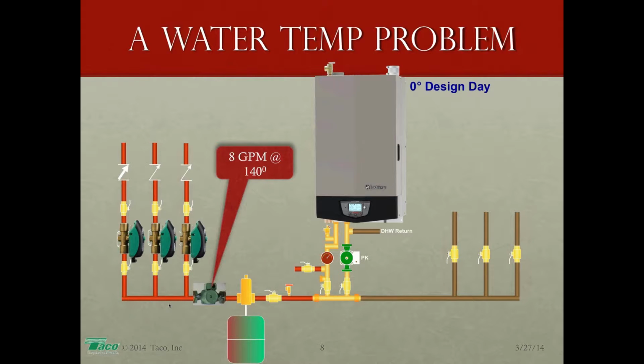So 8 gallons a minute, and we've done our design calculations, and we have found that the system will require 140-degree water. Let's say I'm using panel radiators, and I've sized everything for 140-degree water. So 8 gallons a minute at 140 degrees. On the return side, since I have a 20-degree delta T, it's 8 gallons a minute. My flow rate's still the same, but the return water temperature will be 120 degrees under design conditions. For a modulating condensing boiler, this rocks, because at 120 degrees we're going to condense almost all the time. This is good stuff.